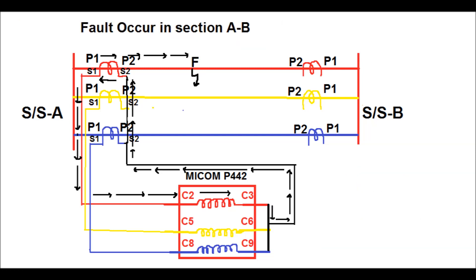Whenever a fault occurs at point F between substation A and B, the current will flow from P1 to P2 in the primary side. In the secondary side, the relay will see the fault in the forward direction and it will send a trip signal to the circuit breaker associated with substation A to clear the fault.